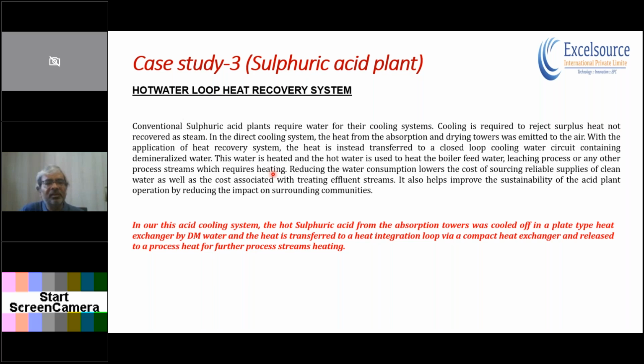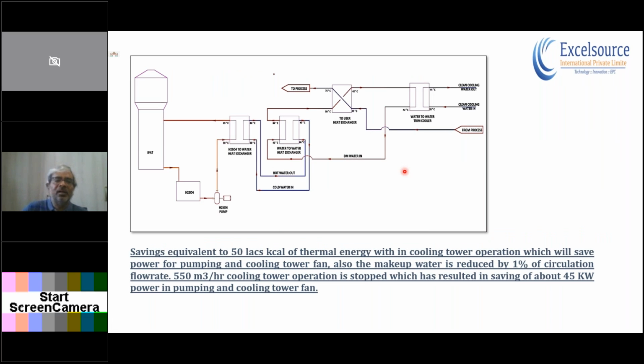So one more example of a heat recovery loop is in the sulfuric acid plant, which I was explaining earlier in my presentations. You know, in an old sulfuric acid plant, even in a new sulfuric acid plant, the absorption tower is basically releasing the heat into the cooling tower. So what we have done, we have not thrown the heat into the cooling towers, and we have used four heat exchangers in a closed circuit, because anybody in the sulfuric acid plant will have a question about what happens if the sulfuric acid leaks into the closed circuit. So we have basically transferred the heat into a closed circuit by generating hot water, and then put one more heat exchanger where this circuit is utilized, so it has completely detached the system from the sulfuric acid plant to the other area of the plant.